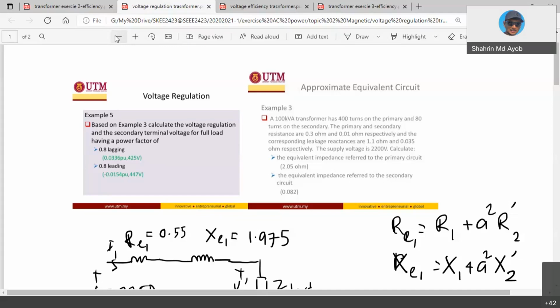So right now let's look at the example of voltage regulation, example 5, from the notes. Based on example 3, calculate the voltage regulation and the secondary terminal voltage for full load having power factors of 0.8 lagging and 0.8 leading. I have done the solution, but only for the lagging case. I hope after this you can try to do the same example for when the power factor is leading.